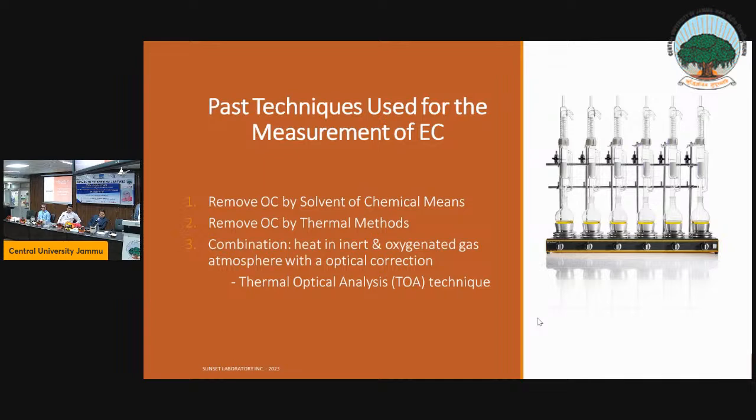And then one day the instrument broke down, and it broke down in the inert phase. And so they found out when they opened up the oven, because they were using an organic standard, and they knew that this standard was clear when they put it on the filter, because they just wanted to calibrate. And when they opened the instrument, the filter was black or brown. And so they scratch their head and they say, well, why is it brown? We didn't put anything brown in the instrument, or black. And the reason is that the sugar pyrolyzed.